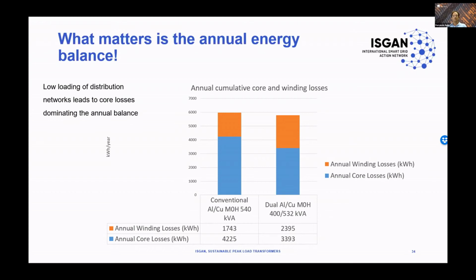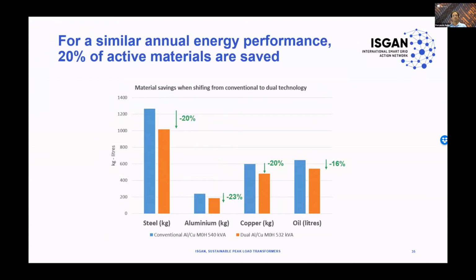So significant savings. The advantage of the second, more compact design is okay. Energy-wise, it's quite the same, but the advantage is material use. We are seeing that in the next slide. So if we represent here the amount of steel consumed by these two units, which are equivalent in peak load and equivalent in energy performance, we see that steel is reduced by 20%.